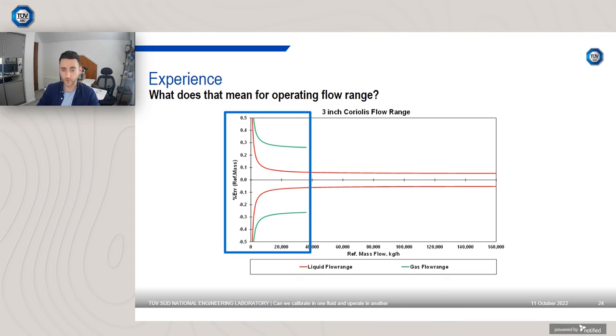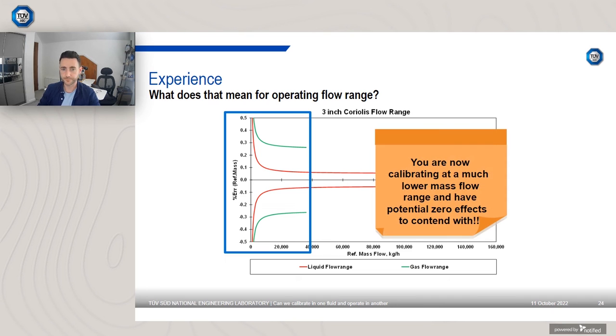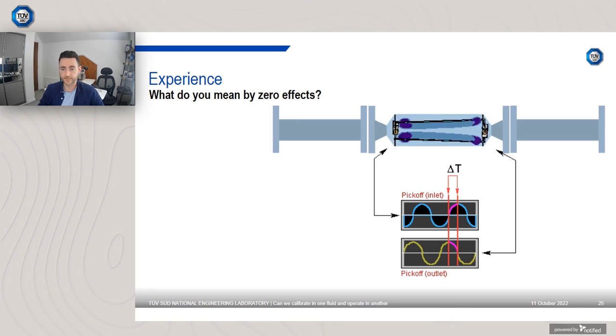Coriolis meters do work well in both liquids and gases, but if you're trying to calibrate them in gas, then you have to be aware of the different flow range, and crucially you have to be aware of the fact that zero effects are potentially going to dominate some of your results down at the lower end. So as I say, you're now calibrating a much lower mass flow rate range and potentially have zero effects to contend with. So what do I mean by zero effects?